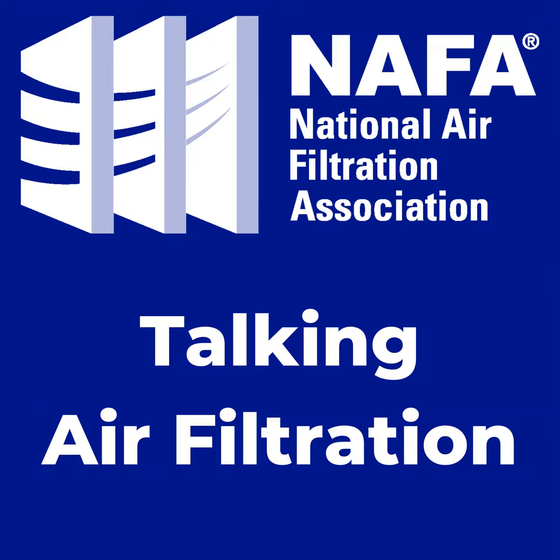However, it isn't always positive. This is a MERV 15 media that we evaluated with nanofibers, and the main thing I'm pointing out is the dust holding capacity. It took us 4 grams of dust to reach our final loading point, versus a traditional MERV 15 media with electrostatic charge on it. So that's something I think we need to overcome. I think different test methods or different applications for the fibers can boost that dust holding performance, but I'll talk about that in a little more detail.